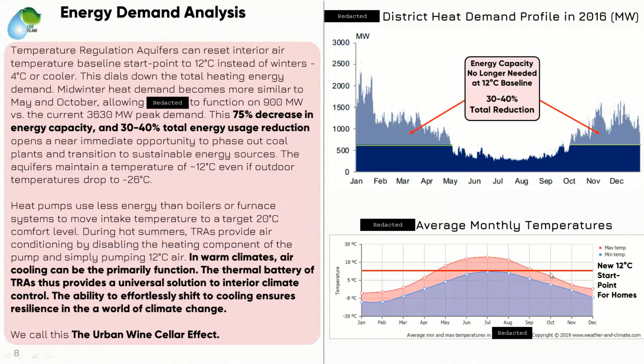We know what their demand is for heating energy during those months, so let's assume that's consistent throughout the rest of the year. That means we can cut these peaks off, we don't need these high peaks anymore. This orange line is going to be the new energy demand profile, because you're heating from 12 degrees Celsius, no longer from -8 or -26 outside, which is what you'd be pumping hot water in to fight against.